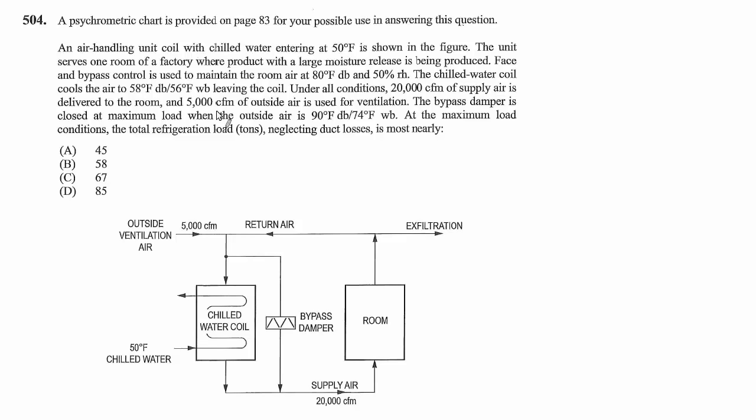Room air is maintained at 80°F dry bulb and 50% relative humidity. The chilled water coil cools the air to 58°F dry bulb, 56°F wet bulb leaving the coil under all conditions. 20,000 CFM of supply air is delivered to the room and 5,000 CFM of outside air is used for ventilation. The bypass damper is closed at maximum load when the outside air is 90°F dry bulb, 74°F wet bulb.